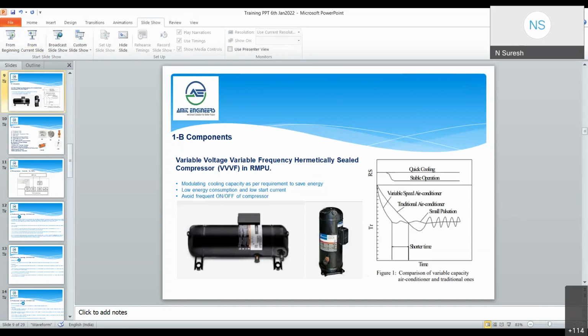Now I'm going to cover the component level, like the variable frequency compressor, which is newly introduced in Train 18. The purpose of using this compressor is to have some energy saving, to modulate the cooling capacity. The compressor will run at lower voltage and lower frequency so that the energy consumption can be reduced. Particularly, between the horizontal compressor and the vertical compressor, there is a small difference. This will be slightly bigger in size. Since it is horizontal, there is one additional oil pump in the mechanism to have better oil circulation.